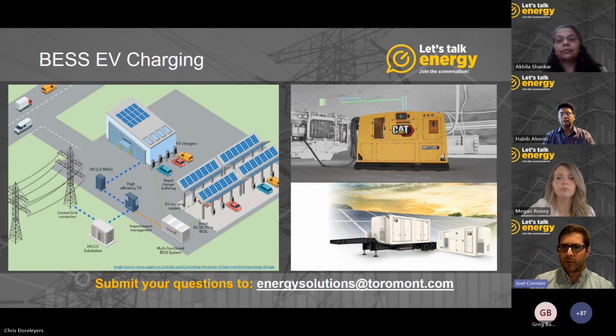So to provide an example, let's say a large percentage of the population switches to electric vehicles, we may see a new peak demand time around 4:30 or 5 p.m. Monday through Friday, when we all get home from work and we plug in our cars to charge. Some existing utilities may not be prepared for this new peak demand load. So by utilizing battery energy storage system solutions with charging stations, we can charge the batteries during the off-peak hours and then discharge the stored energy during those peak hours. This solution will help provide stability to utilities and also reduce peak demand charges for the owner of those charging stations and reduce their utility costs. And a battery energy storage system would also allow a charging station to be operated with a limited capacity, of course, during a grid power outage.